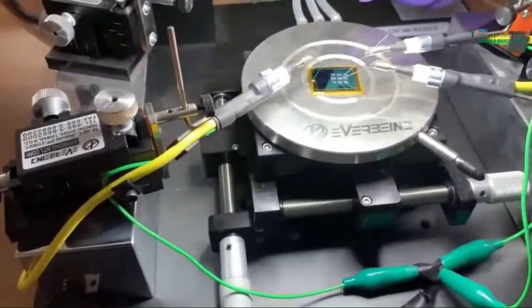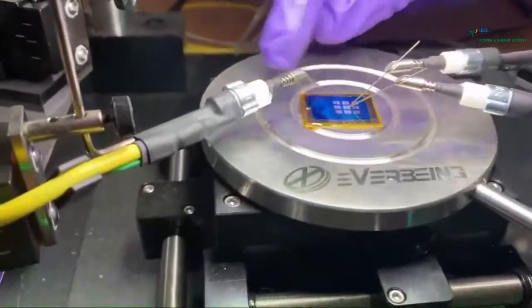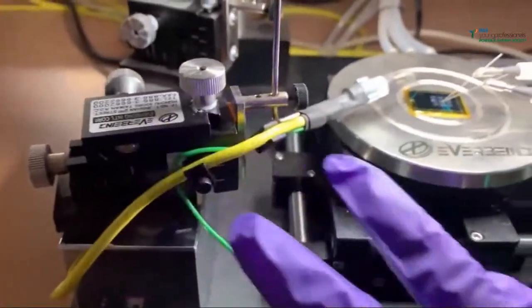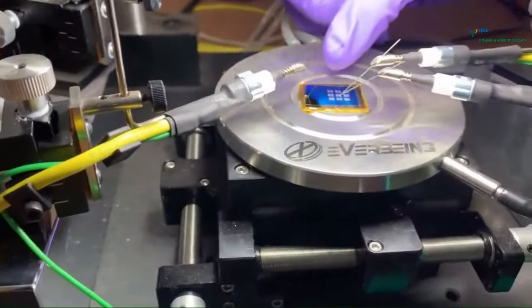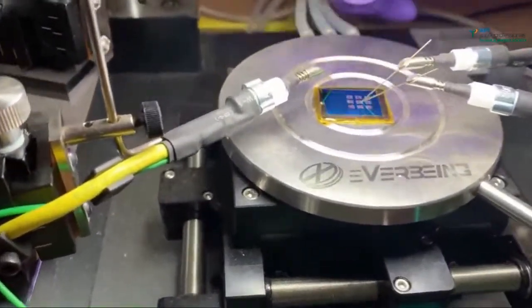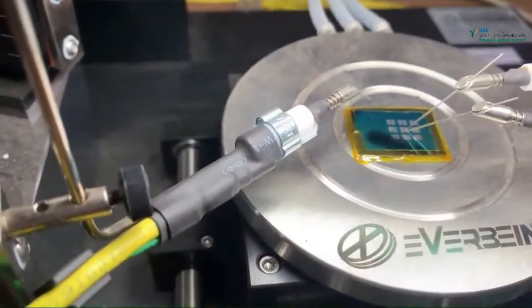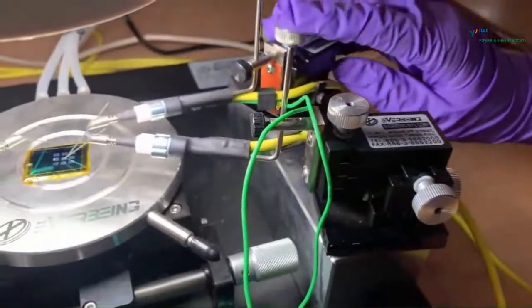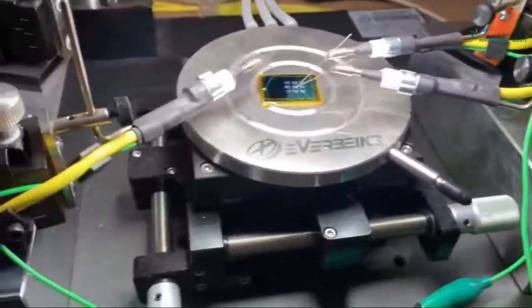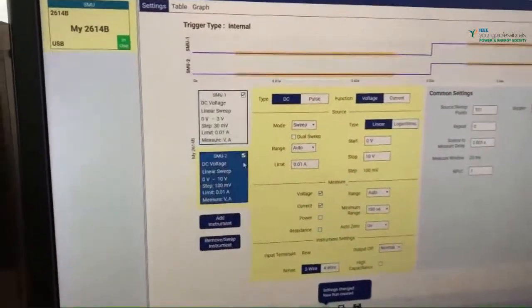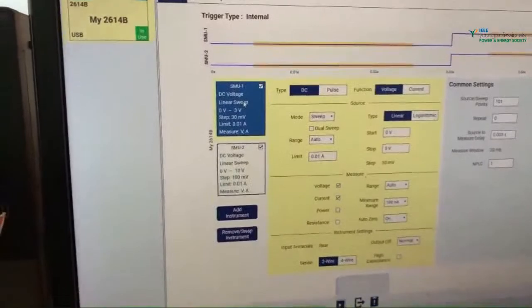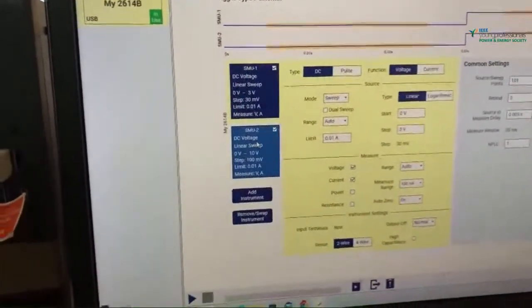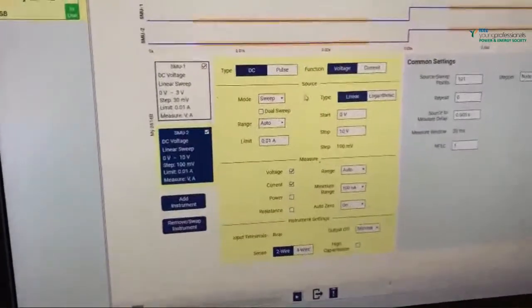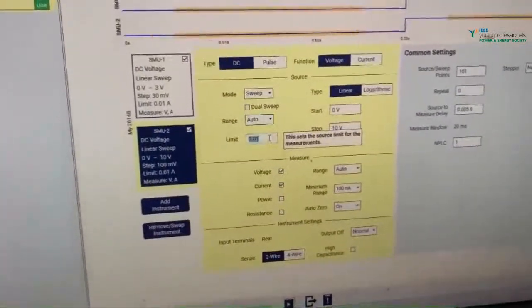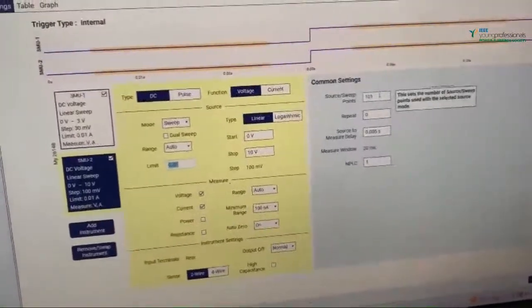Here we have a back gated device. This probe is used to connect to the gate. It is directly connected to the chuck, so the back gate connection will be available there. And this is the drain, and these are the source connections. In the software, we'll be enabling both source measurement units, SMU1 and SMU2. Our gate is connected to SMU1 and our drain is connected to SMU2. Here the sweep mode, the current limit, and the source points, etc., will be given.